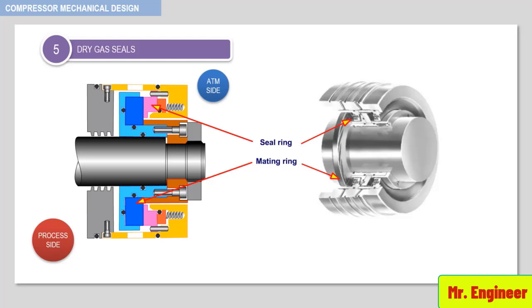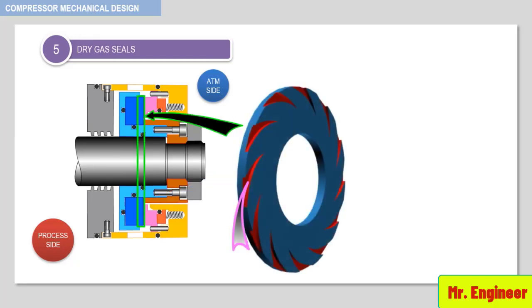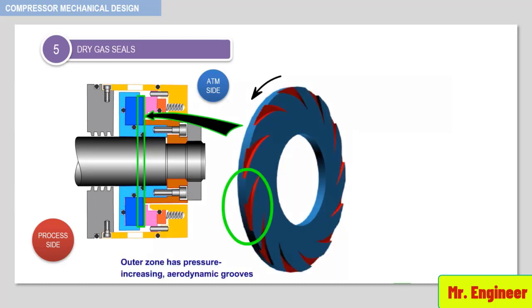The non-contact gap is maintained by a pressurized buffer gas or process system. The sealing face of the rotating seat has the outer zone machined with pressure-increasing aerodynamic grooves. This is where the gas enters.